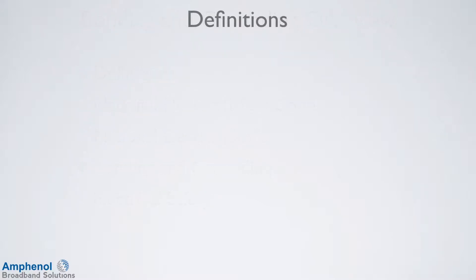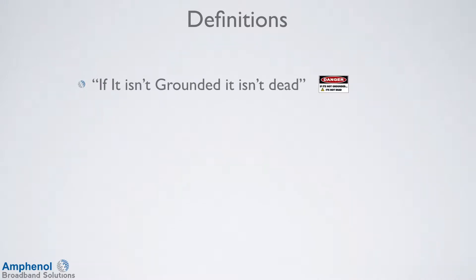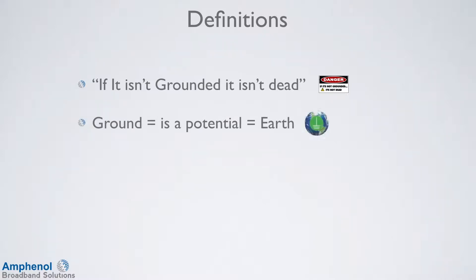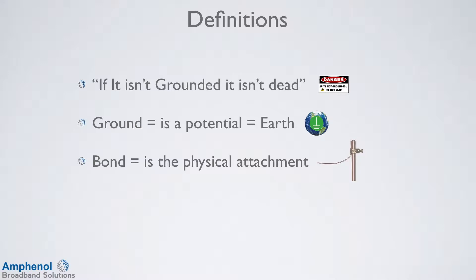Before we look at electrical definitions, remember this important safety tip: if it isn't grounded, it isn't dead. Unless it is verified, consider all conductors to be energized. We'll also cover additional safety items later in the video. Grounded is a potential in the earth — it doesn't mean it is zero voltage and no current. A bond is a physical attachment to power or telco grounds.